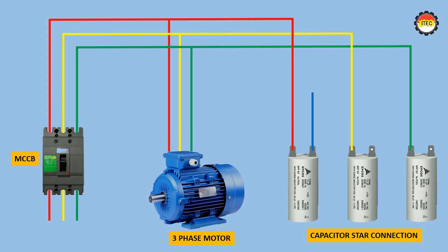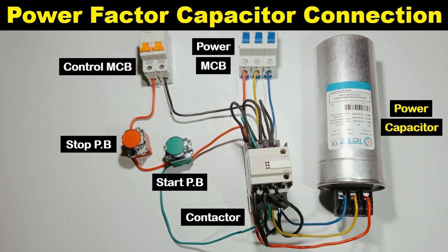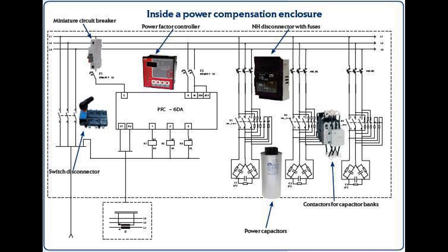Harmonic distortion can degrade power quality, leading to equipment malfunction, increased losses, and reduced efficiency in electrical systems. Detuned capacitors improve power quality by reducing harmonic distortion, resulting in smoother voltage waveforms and more reliable operation of electrical equipment. Resonance occurs when the natural frequency of the electrical system matches the frequency of harmonic currents or voltages. Detuned capacitors prevent resonance by tuning to a frequency different from the harmonic frequencies, avoiding amplification of harmonic voltages and mitigating the risk of equipment damage.